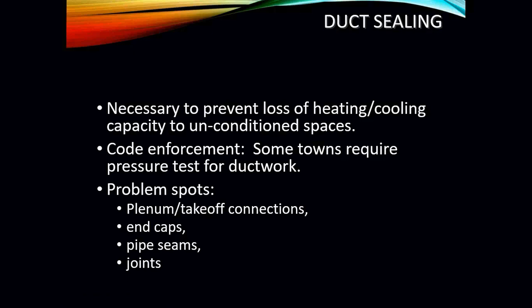Problem spots where you'll most likely run into leaks are your plenums, takeoff connections, any end caps in use, any pipe seams, and any joints in that piece of ductwork. Bottom line: you need to make sure you're sealing every piece of ductwork there, whether it's an adjustable elbow, a stacked duct, flexible duct, whatever it is, it all should be sealed. If not, you're running a risk of losing valuable air and pressure into spaces where it's not good to do.